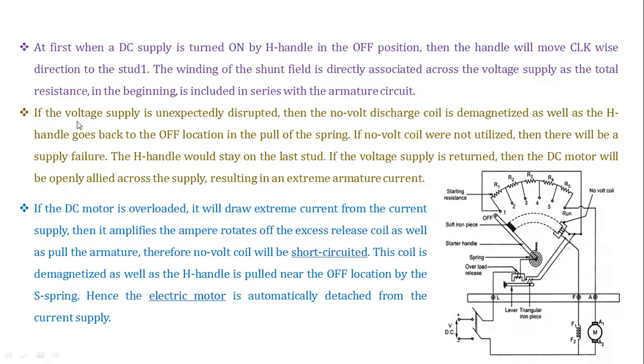Next point: what exactly happens if the voltage supply is unexpectedly disrupted? Then the no volt coil is demagnetized, and the handle goes back to the off position under the pull of the spring. If no volt coil were not used, then on a supply failure the handle H would stay on the last step. If the voltage supply is then restored, the DC motor would be directly connected across the supply, resulting in a high armature current.